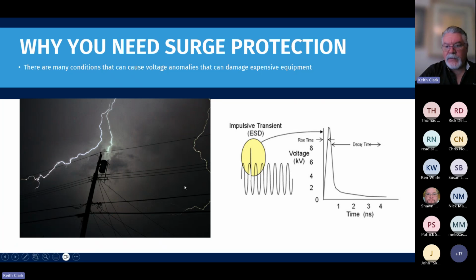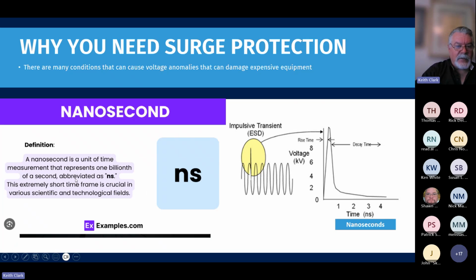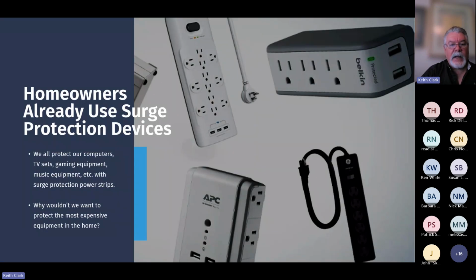Impulsive transient surges are measured in nanoseconds. A nanosecond is a unit of time measurement that represents one billionth of a second, so it's an extremely short time frame. And that's why a line monitor, for example, doesn't look at things in nanoseconds. It needs a little more time to recognize that there is actually a problem. This is a unique event. It's a rapid, high energy, high heat type of event that takes a surge protection device to deal with it.